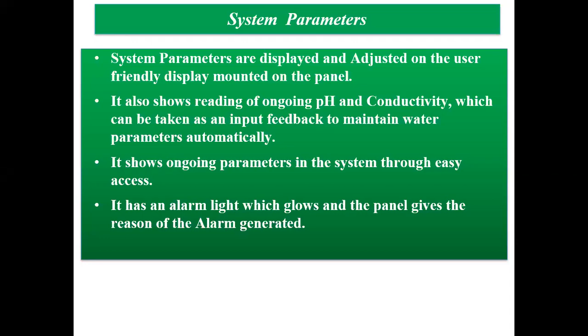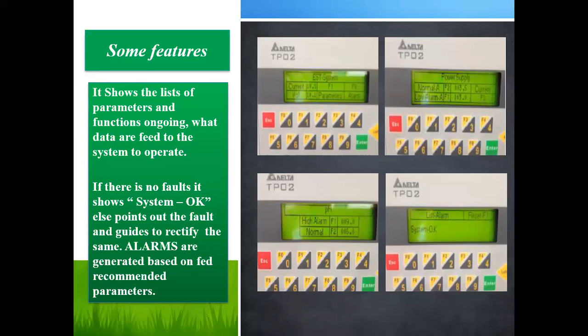Thereafter you should have an alarm system which gives an alarm when the pH is going high, or the conductivity is going high, or excess blow down is occurring. Certain pictures of systems are shown, like alarms being displayed or system okay being shown. If there's no alarm, system okay is shown, or a high alarm appears, but you can set the values, for example if a high alarm needs to be given after pH level 8.5.